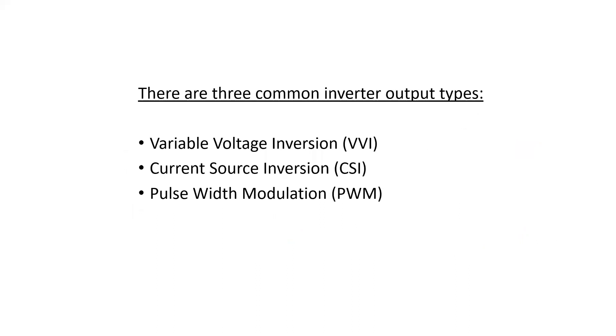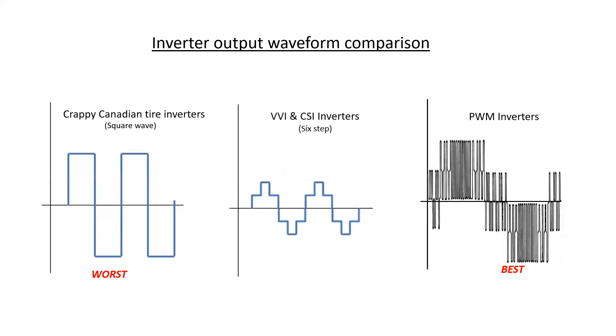There are three common inverter output types: Variable Voltage Inversion (VVI), Current Source Inversion (CSI), and Pulse Width Modulation (PWM). Their waveforms include a square wave at the most basic level — simply a long burst of DC in the positive and then a long burst in the negative. None of these waveforms really look like a true sine wave; they basically look like a rough approximation of one.